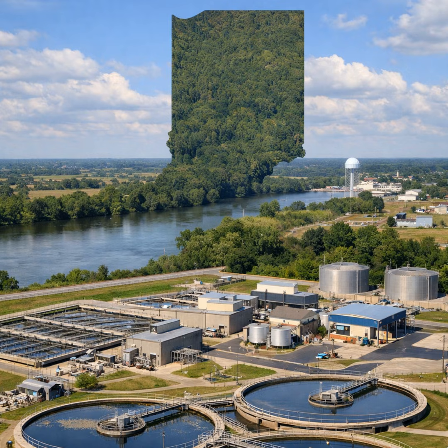Struvite, a deposit or precipitate of magnesium ammonium phosphate hexahydrate found on the rotating components of centrifuges and centrate discharge lines. Struvite can be formed when anaerobic sludge comes in contact with spinning centrifuge components rich in oxygen in the presence of microbial activity. Struvite can also be formed in digested sludge lines and valves in the presence of oxygen and microbial activity. Struvite can form when the pH level is between 5 and 9.